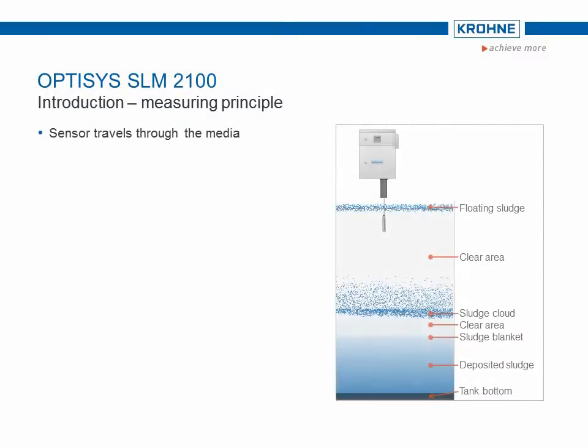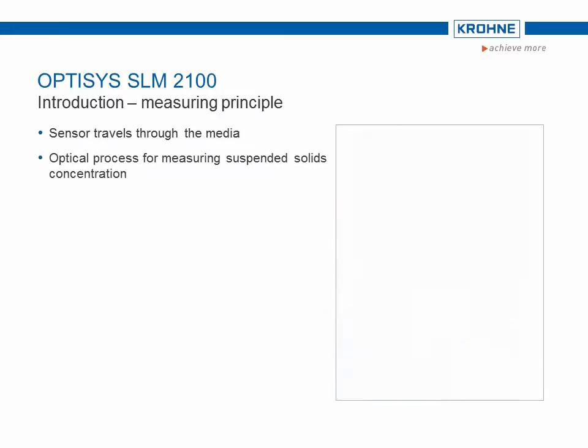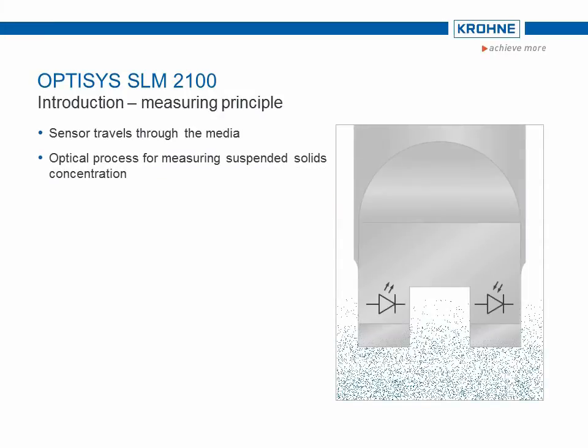In contrast to the widely used ultrasound principle, the SLM2100 uses an optical sensor that is immersed in the medium to measure the concentration of suspended solids at different depths. The sensor travels up and down through the medium, continuously monitoring the local concentration of suspended solids content in the medium.